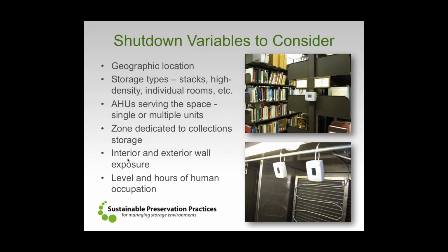Now, the variables we have to think about in here, essentially what's going to cause the space to go out of set point or out of range when we start to turn our mechanical system off. If we live in a really hot climate, this is a lot harder to do. Although I will say that we experimented and tested it in Birmingham, Alabama, and we could still achieve shutdowns in the summertime after some experimentation.